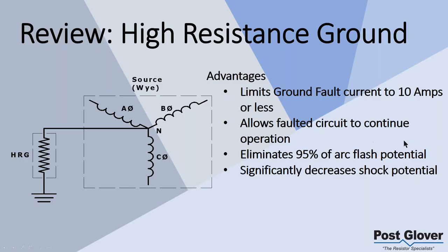It allows a faulted circuit to continue to operate. That's one of the benefits of high resistance ground. It's called high resistance ground because it's a higher ohmage and less current, since they're inversely proportional. So the highlights: it allows a faulted circuit to continue to operate, limits a large percentage of your arc flash potential, and significantly decreases shock potential due to stray ground currents. This is going to be one of the components of a hybrid grounding system, so I wanted to introduce it to you if you haven't already seen it.